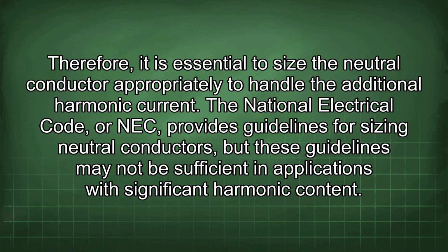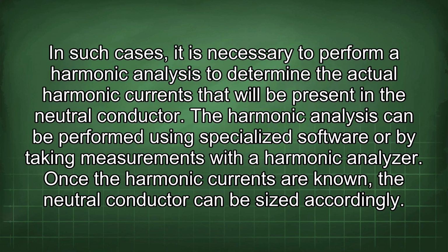The National Electrical Code, or NEC, provides guidelines for sizing neutral conductors, but these guidelines may not be sufficient in applications with significant harmonic content. In such cases, it is necessary to perform a harmonic analysis to determine the actual harmonic currents that will be present in the neutral conductor. The harmonic analysis can be performed using specialized software or by taking measurements with a harmonic analyzer. Once the harmonic currents are known, the neutral conductor can be sized accordingly.